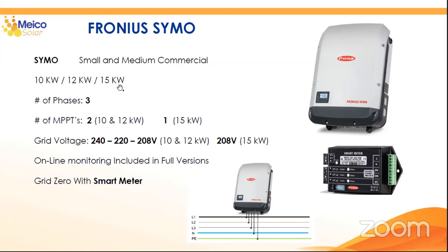Because of the power levels, it's normally for small and medium projects. The powers we have here are 10, 12, and 15 kilowatts. As I told you, we have three phases at the output of the inverter, and importantly, two MPPTs for the 10 and 12 kilowatt versions, and only one MPPT for the 15 kilowatt inverter. The grid voltage for the 10 and 12 kilowatt can work from 240 to 208. With the 15 kilowatt, you can only work at 208 volts.